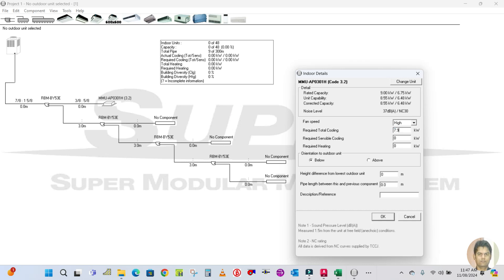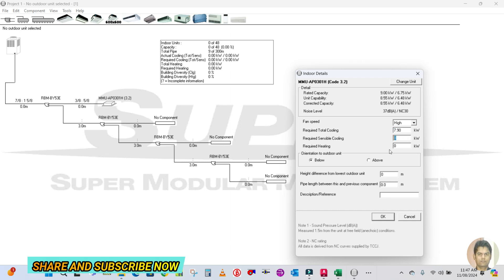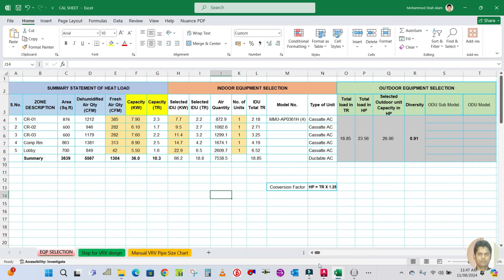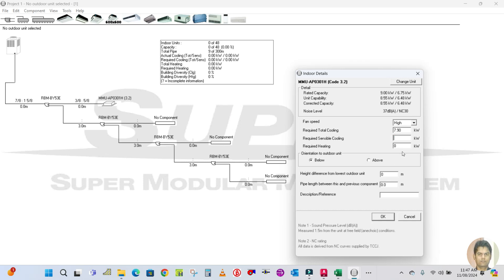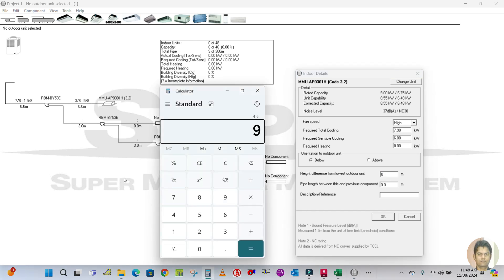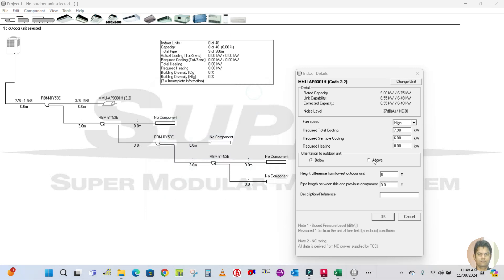The required sensible cooling is — let's say 6.5 or 6. Let's say 6. I don't want heating capacity, I want cooling only. The height difference from the lowest outdoor unit: the building is 9 feet, which is 9 divided by 3.28, approximately 2.7 — let's say 3 meters.